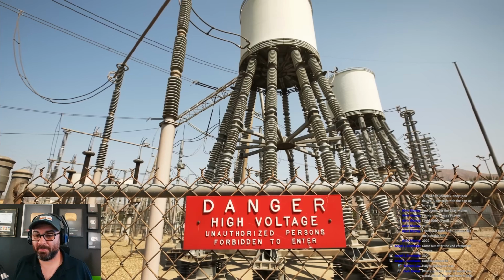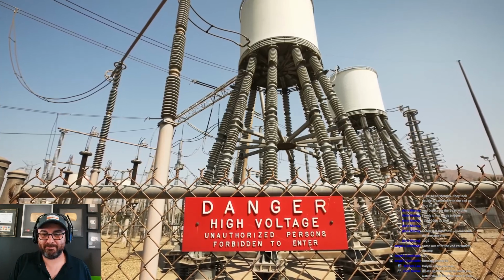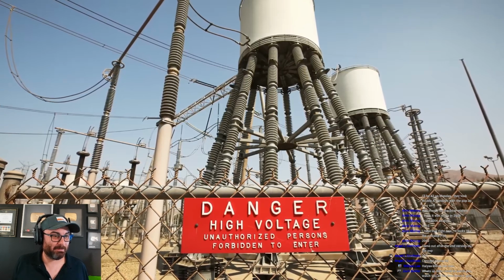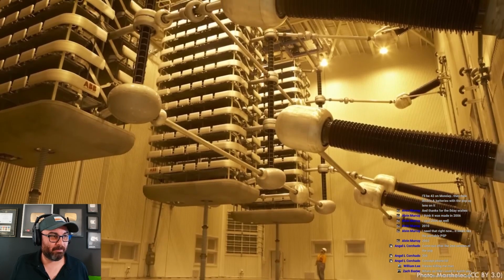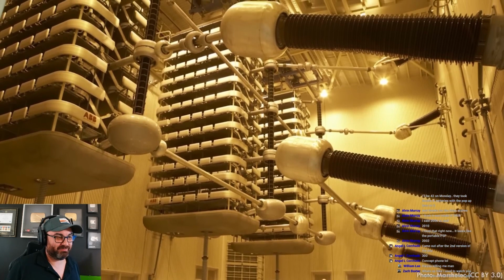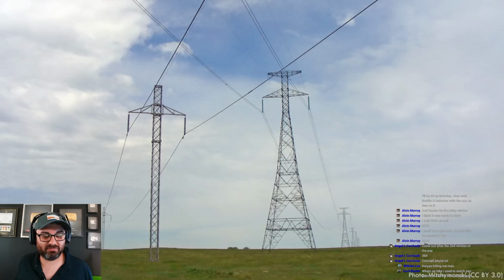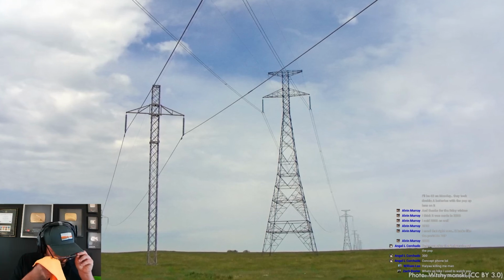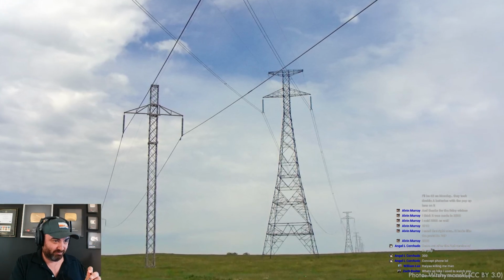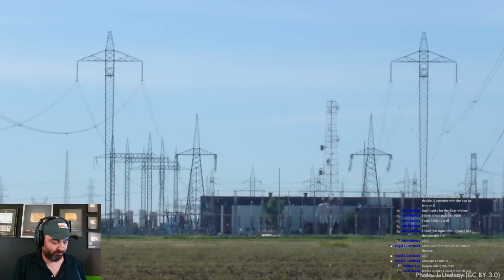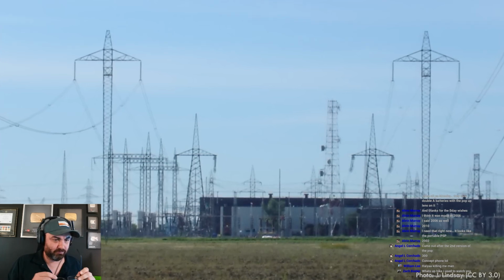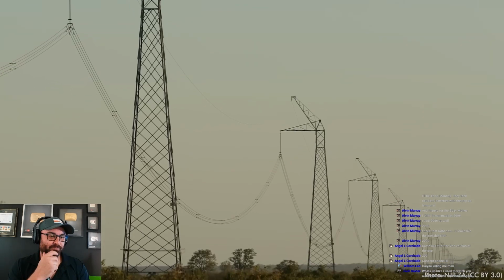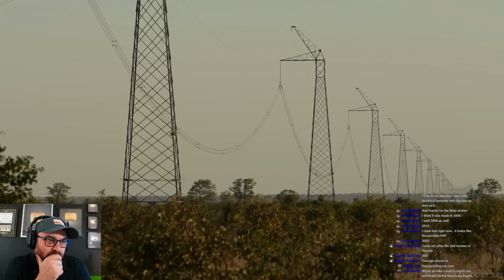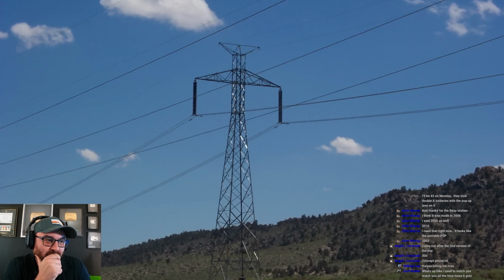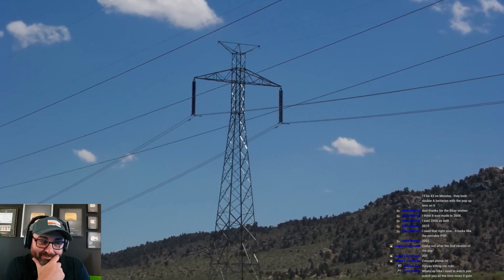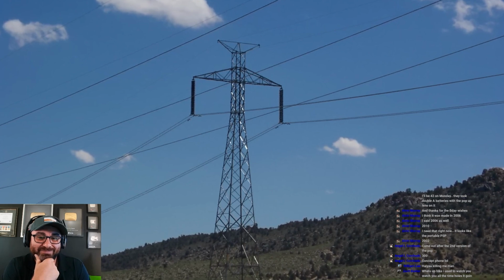Similarly, there are some high voltage transmission lines across the world that use direct current, like a battery, instead of AC. We'll save a detailed discussion of these systems for another day because there's a lot of fascinating engineering involved. But I did want to mention them here because many of these lines are equipped with really elaborate grounding systems. Although most high voltage DC transmission lines use 2 conductors, positive and negative, some only use 1, with the return current flowing through the earth or the sea. And even the bipolar lines often include grounding systems so they can use ground return during an outage or an emergency if one pole is out of service.